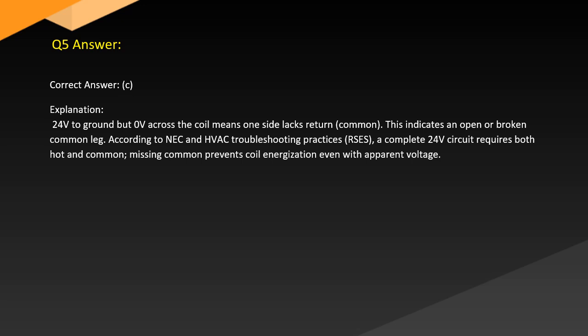Answer. Correct answer, C. Explanation. 24 volts to ground but 0 across the coil means one side lacks return common. This indicates an open or broken common leg. According to NEC and HVAC troubleshooting practices, RSES, a complete 24-volt circuit requires both hot and common. A missing common prevents coil energization even with apparent voltage.